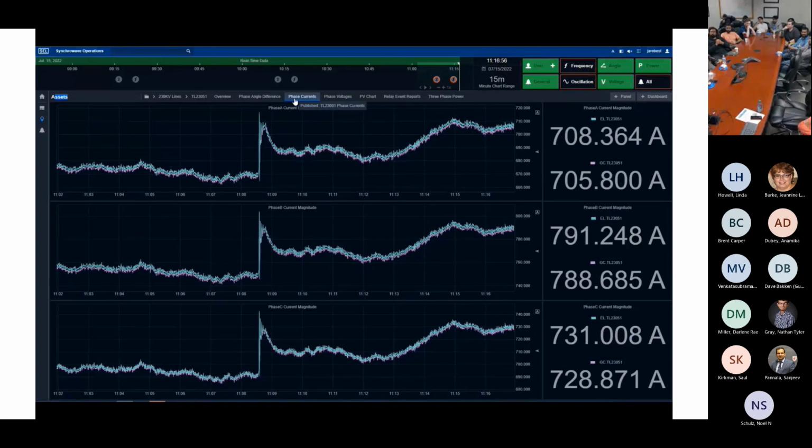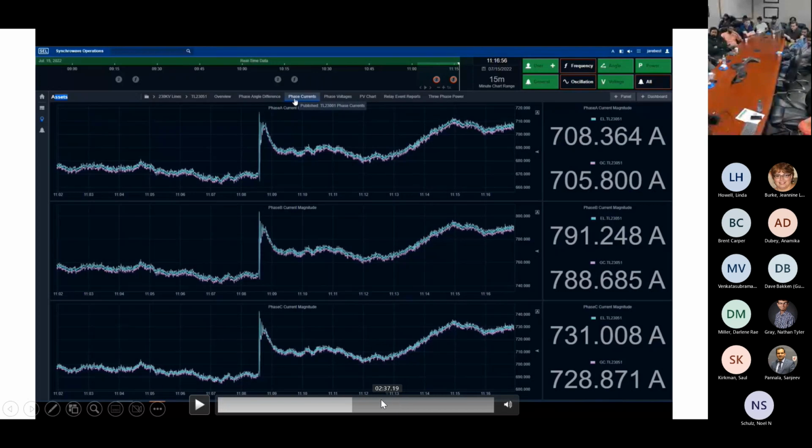So it's interesting that they start using current measurements, something I didn't really expect them to use these current measurements for. It's also nice because obviously they get the breaker state and everything through their SCADA displays, but they also like to get a second opinion, so to speak. Line trips, one phase clears. That's what the targets show. But it's nice to come over here and say, oh, one current is zero, and see it not just as a SCADA number, but see how it evolved and all that kind of stuff. So that's kind of interesting. A lot of times they like to look at currents.